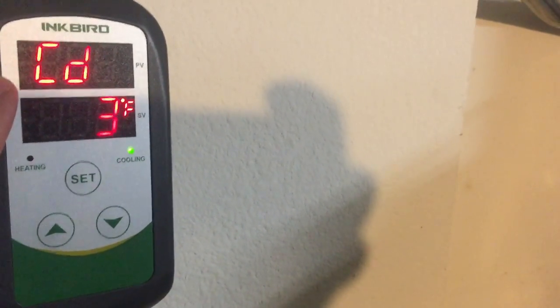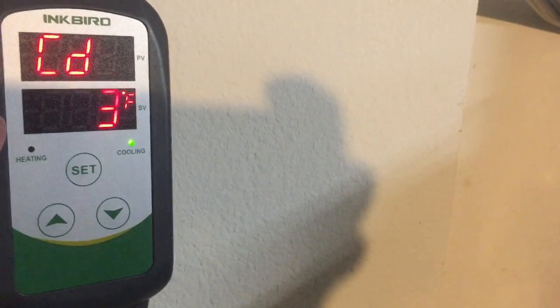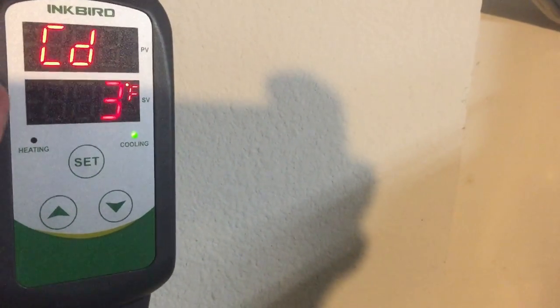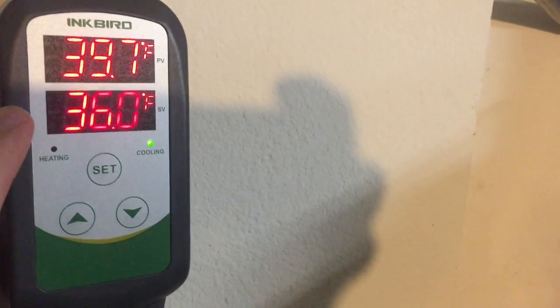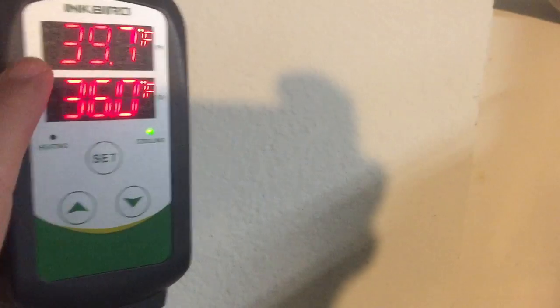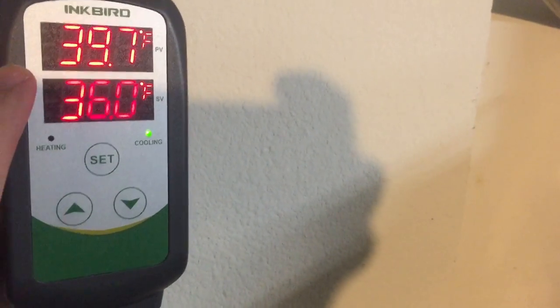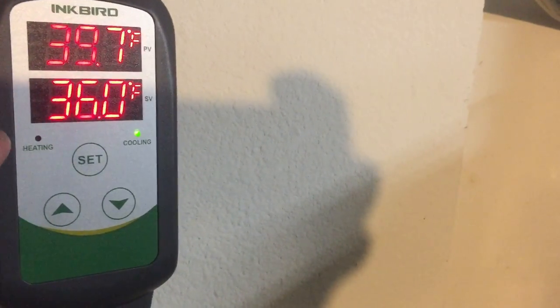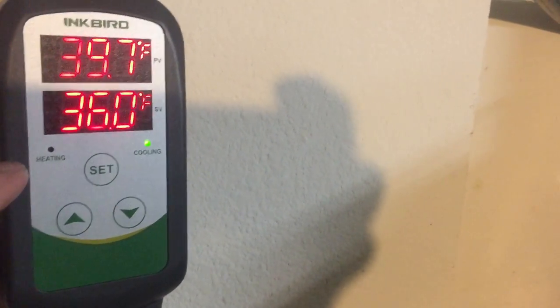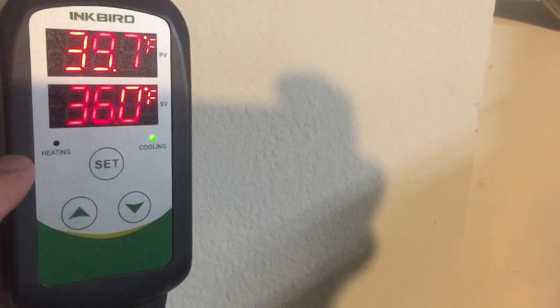This one is the cooling difference, and this is 3 degrees. So this is plus or minus 3 degrees. So if you set it at 36 you're going to run either at 39 or as low as 33.